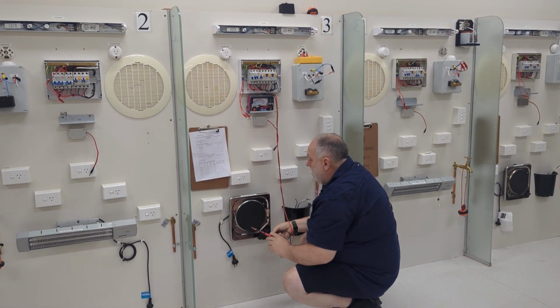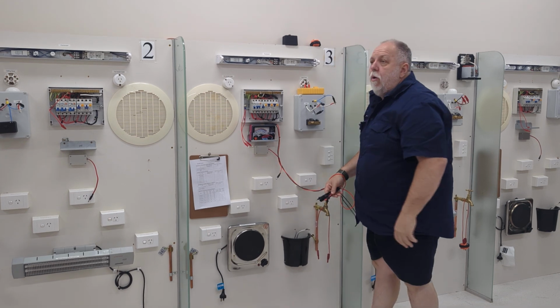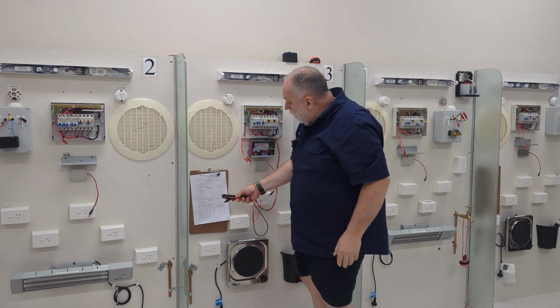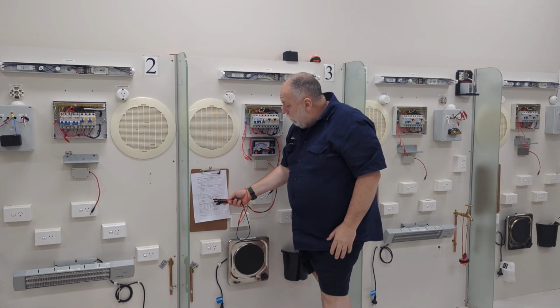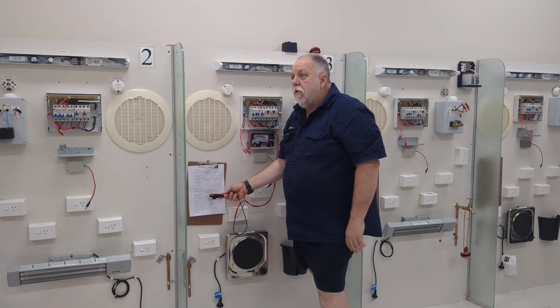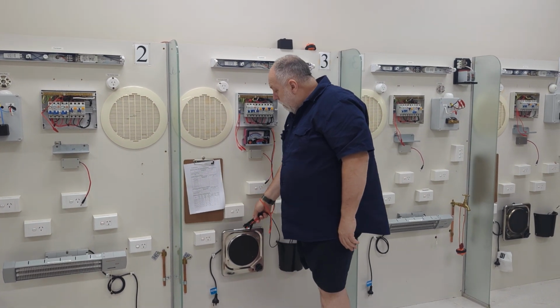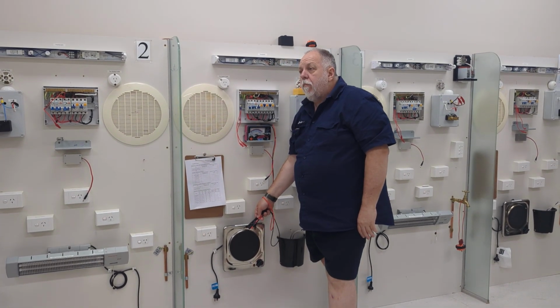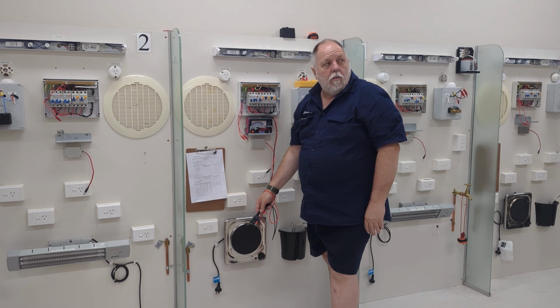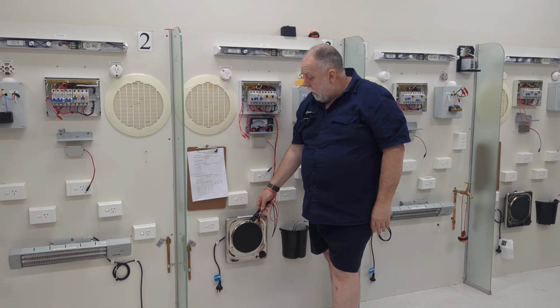And I've got infinity as well. So now I know my appliance is okay. And that's all I'm required to do: continuity of earthing and the insulation resistance test. All right. Minimum reading on this one? 10,000. Sorry? 10,000. 10,000, correct.